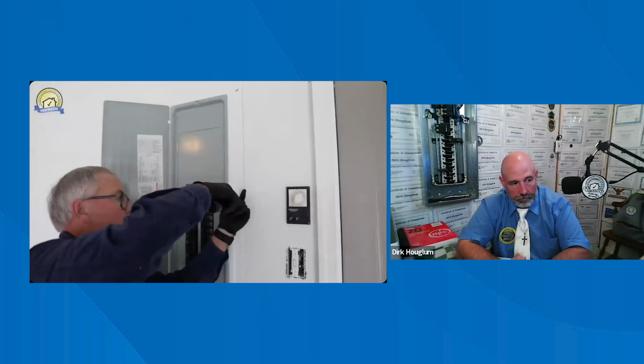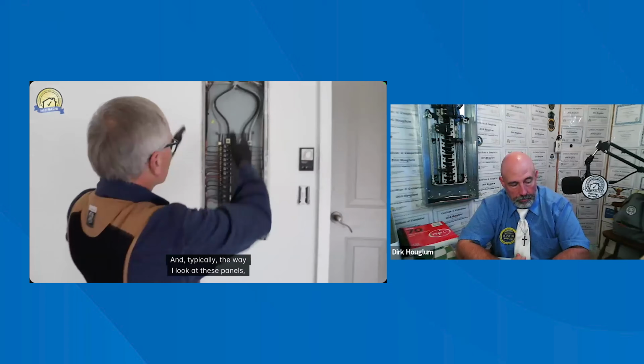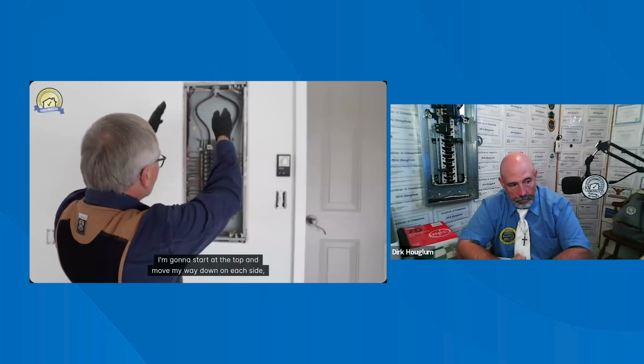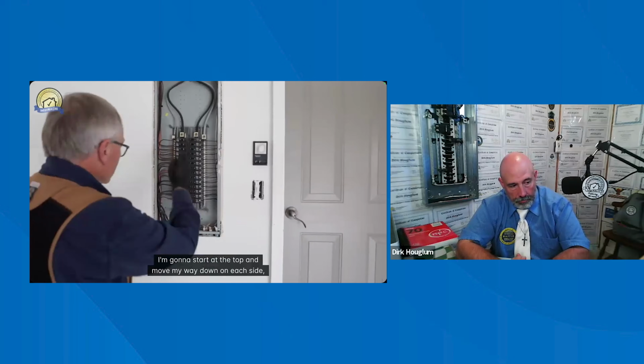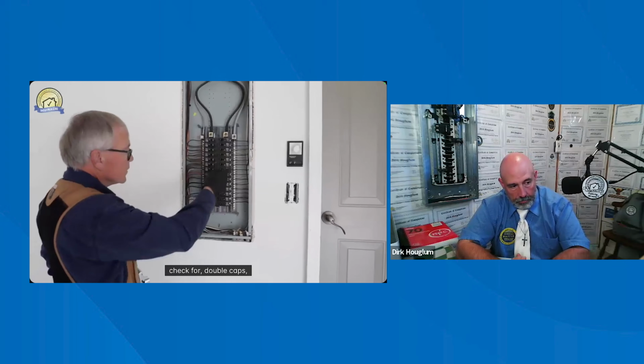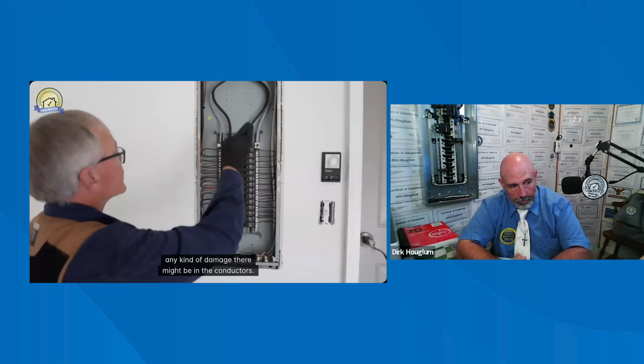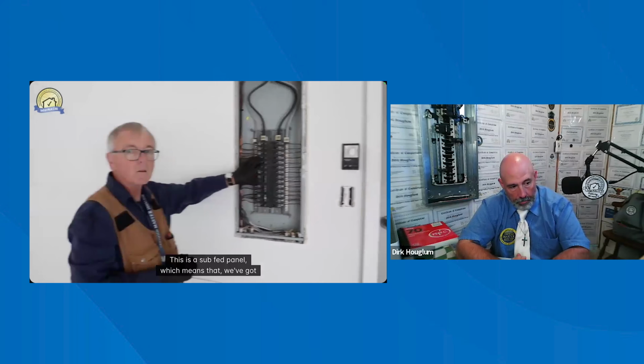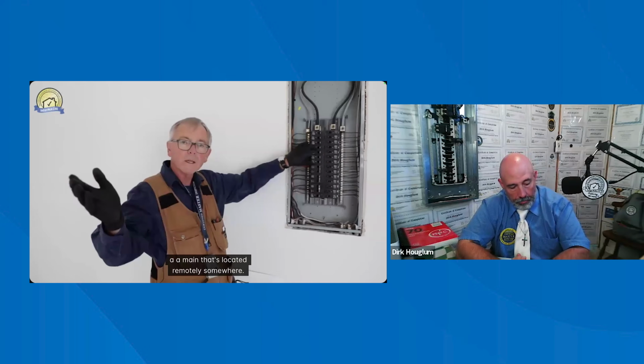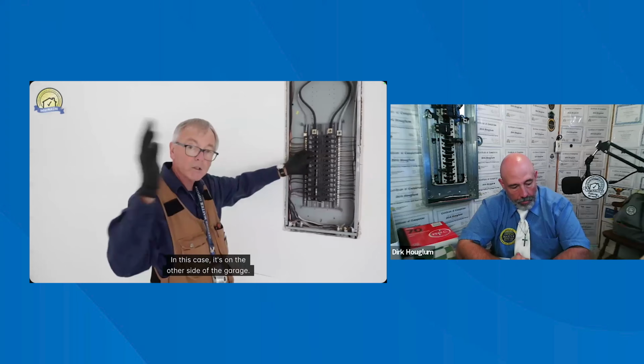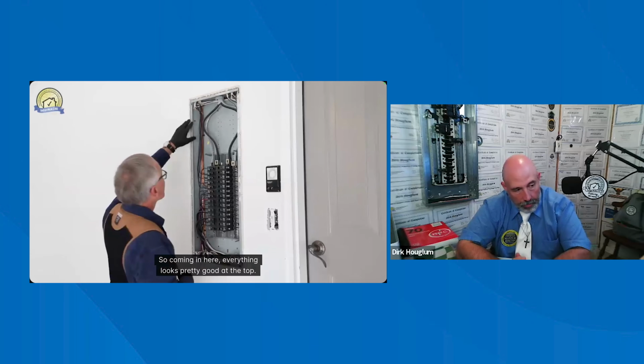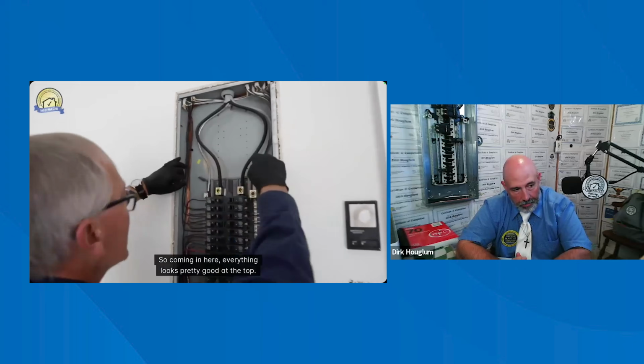Now we're going to take the dead front off the panel. Okay, so now we've got the dead front cover off. Typically the way I look at these panels, I'm going to start at the top and move my way down on each side. Check for double taps, any kind of damage there might be in the conductors. This is a sub-fed panel, which means that we've got a main that's located remotely somewhere. In this case, it's on the other side of the garage. So coming in here, everything looks pretty good at the top.